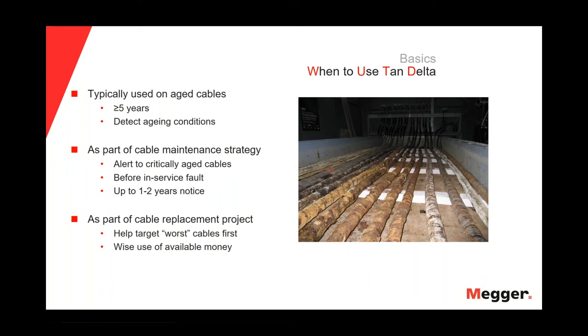And the idea is that if we have, for instance, a big population of old cables and we want to start to replace them, but we have no idea where to start, then the tan delta test will be a very good tool to help us to target the worst cables first. And in this way, we will use the money we have wisely.